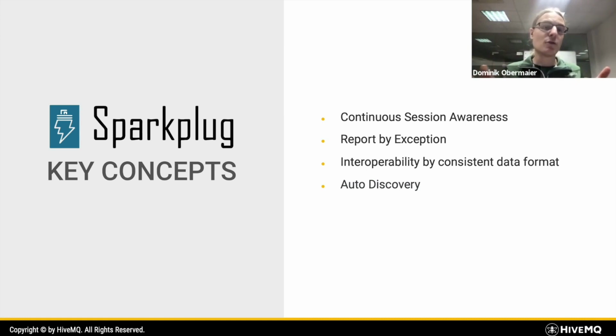Even if you poll every 5 seconds, there's still a 4.99 second window where you miss an actual update. With Sparkplug and MQTT, you get an instant update as soon as something changes. So you get massively scalable architectures where with Sparkplug you can connect all your factories around the globe and have actual millisecond-style communication around the globe, and the only limit is the underlying network.